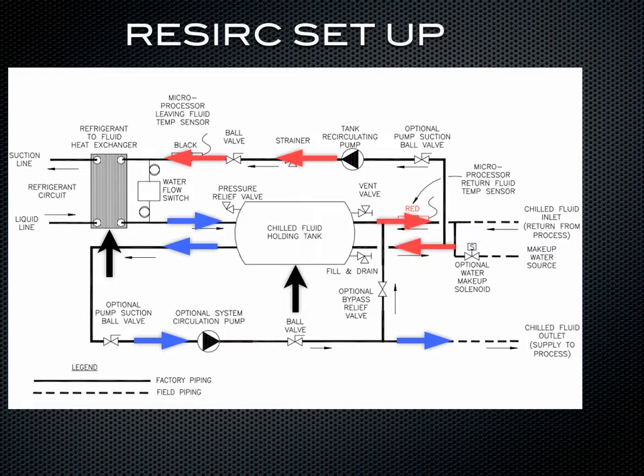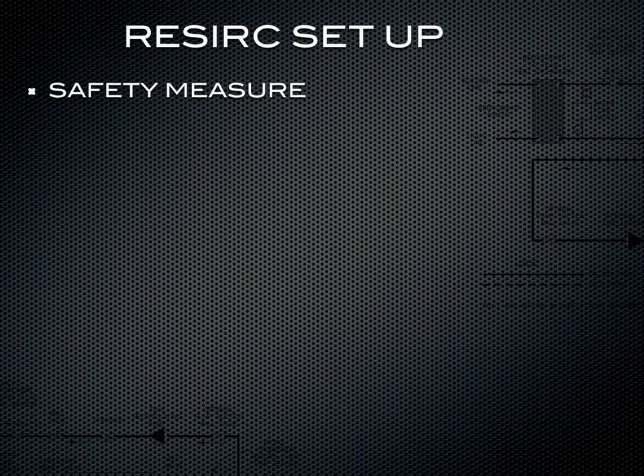You basically have two separate loops acting independently. An important reason to have a recirc setup opposed to a once-through is that the recirc setup can act as a safety measure for your refrigeration system. On a once-through, you have one loop with one pump, so everything is intertwined with the chiller evaporator. If your process goes down or there's a restriction of flow rate, your refrigeration system could potentially shut down. On a recirc tank setup, the recirc pump services the evaporator and keeps your desired tank temperature, while the system pump pulls cold water off the tank to your process. Anything external to the chiller will not affect the chiller refrigeration system.